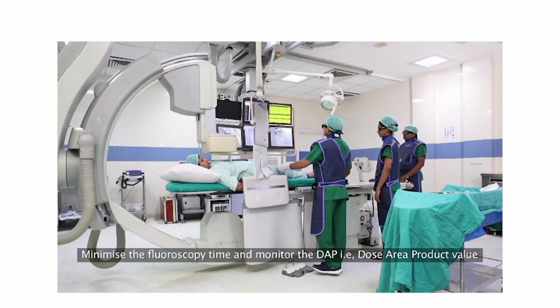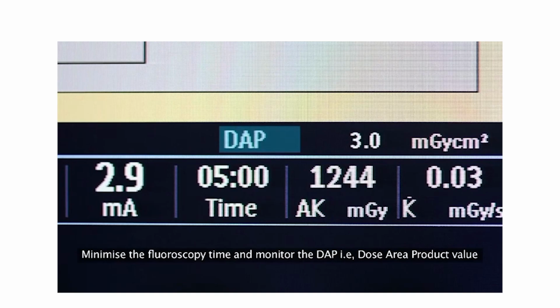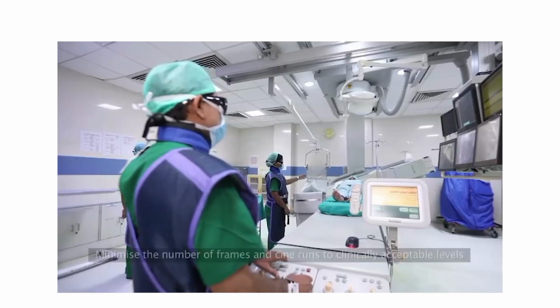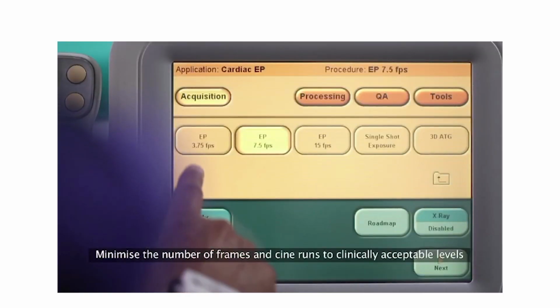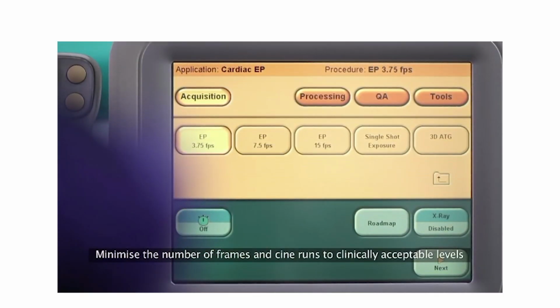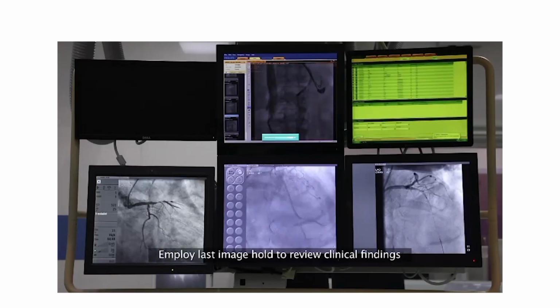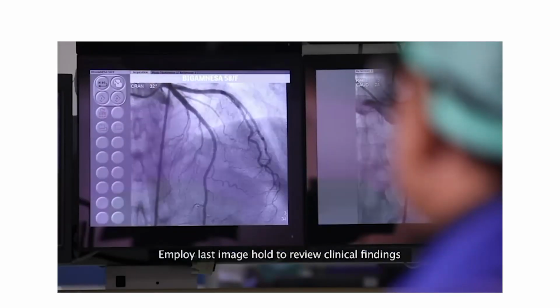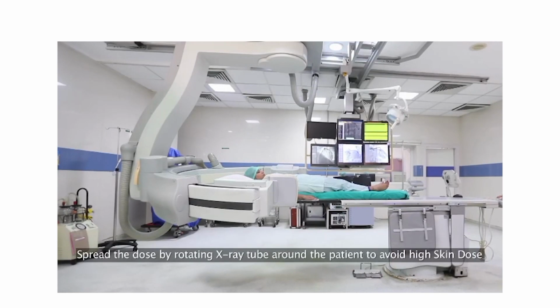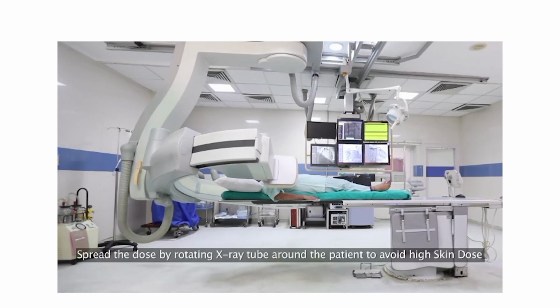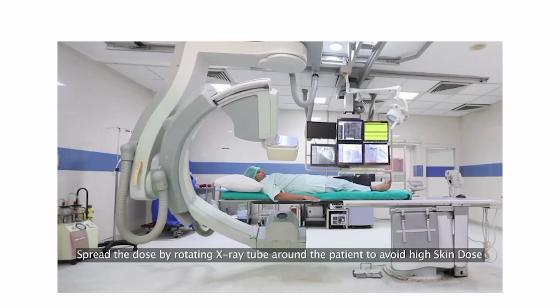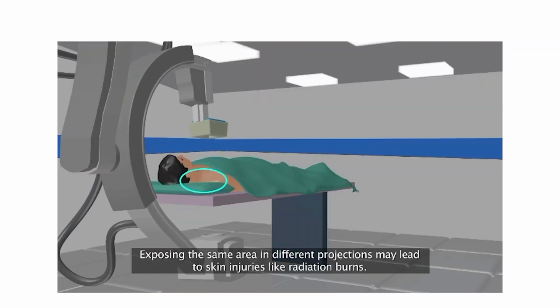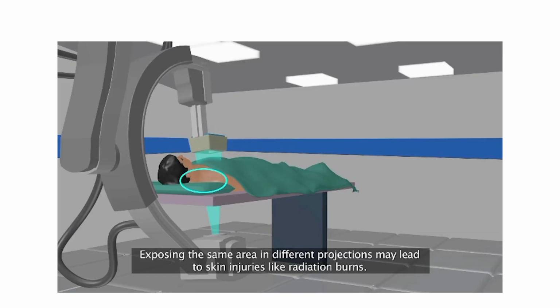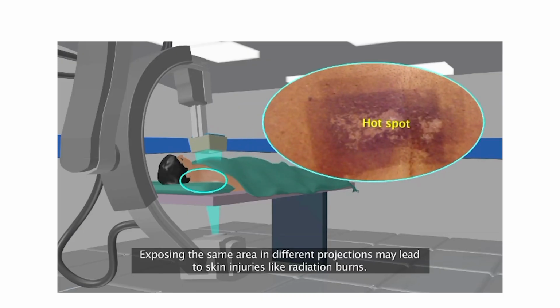Minimize the fluoroscopy time and monitor the DAP, that is, dose area product values. Minimize the number of frames and cine runs to clinically acceptable levels. Employ last image hold to review clinical findings. Spread the dose by rotating the X-ray tube around the patient to avoid high skin dose. Exposing the same area in different projections may lead to skin injuries like radiation burns.